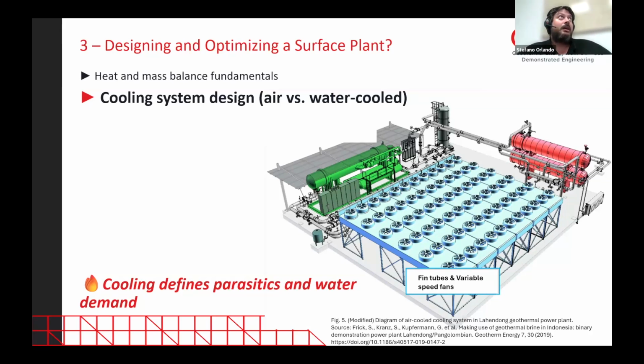Or, for example, with an ORC binary system, I can decide to go for a water-cooled condenser if I have a water source available, like a river, or maybe shallow wells I can use to get water—though it depends strictly on the regulations in that location. If I don't have enough steam and I also want to exploit the brine, I need to go for the dry solution, since that way I have no issue for sure. Lately a new technology is potentially taking place, the ECC—evaporative cooling condenser—which is similar to a dry system but with some water sprayed on top of the pipes to enhance heat exchange with the air.